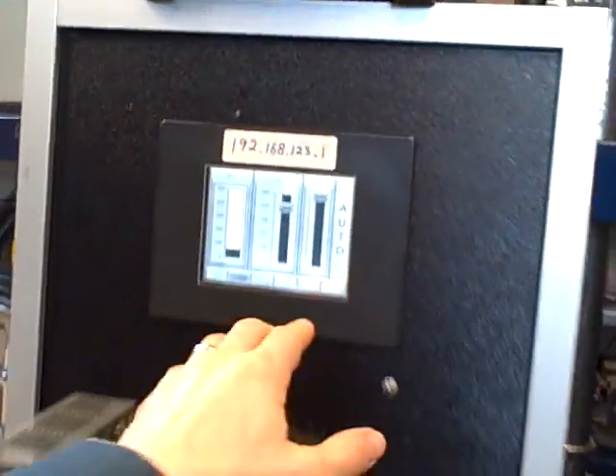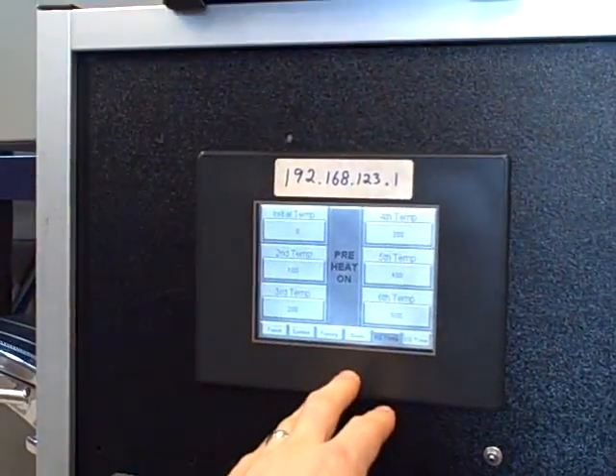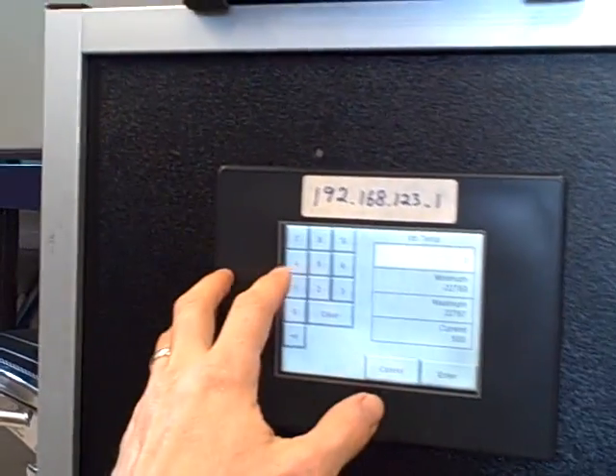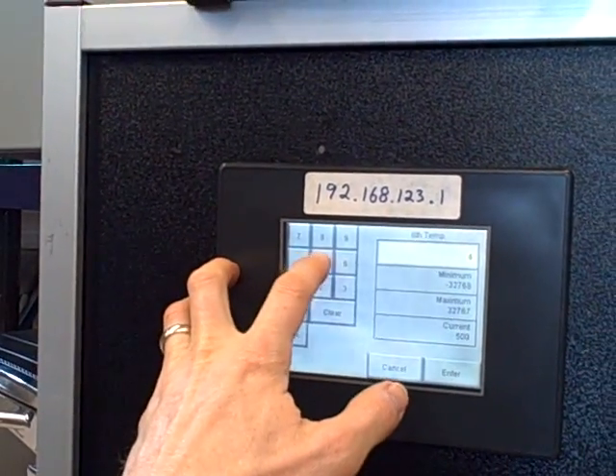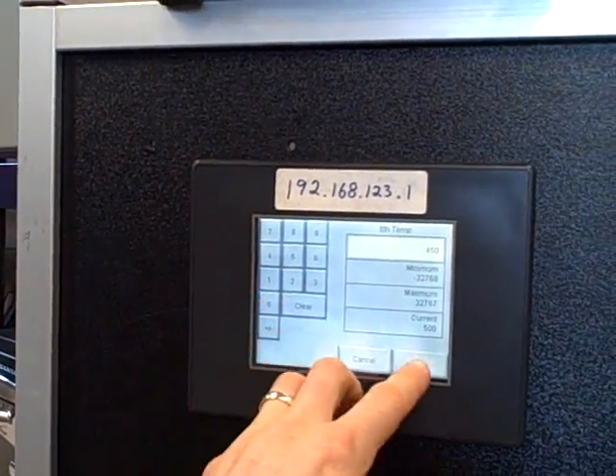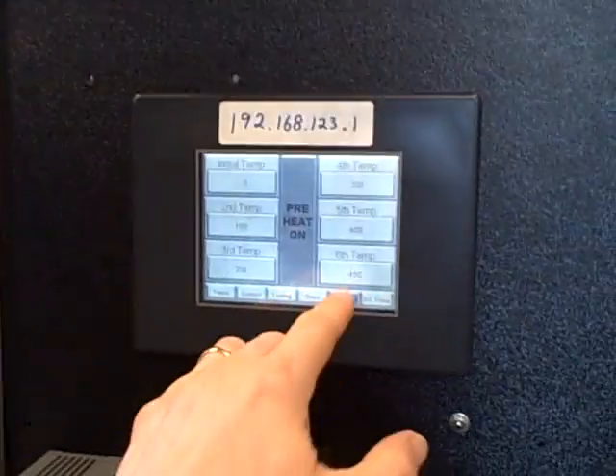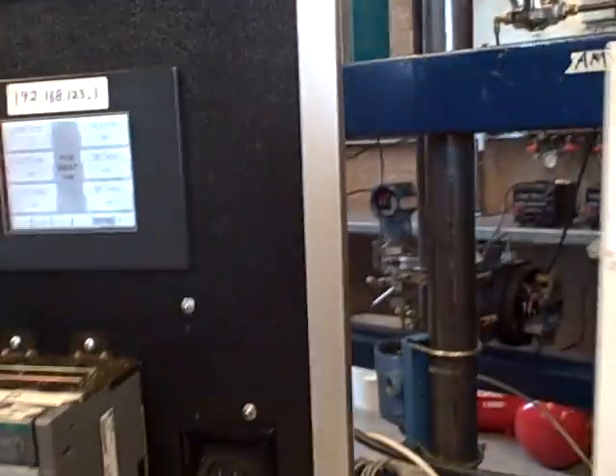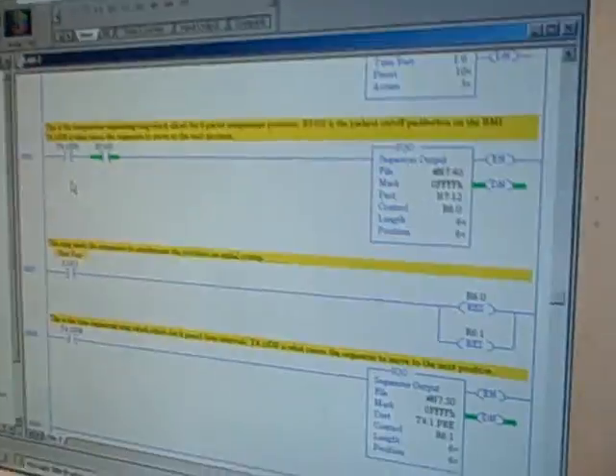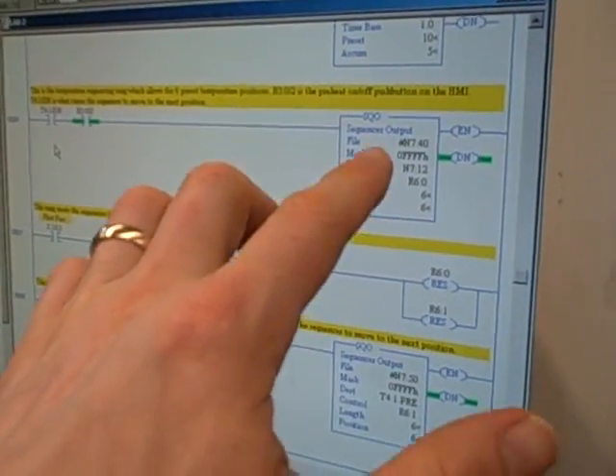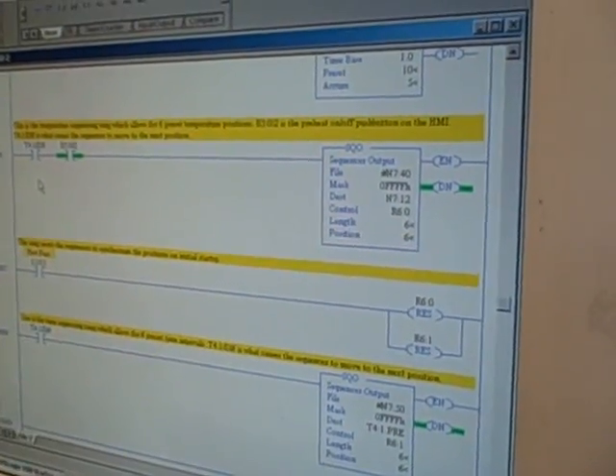So if I go over here, for example, and I go to this temperature, I say, well I want my sixth temperature here to be 450 degrees instead of 500. I can enter that, and what that does is it writes that value into one of the N7 registers in the PLC, and that number just gets picked off by the sequencer output when you get to that position.